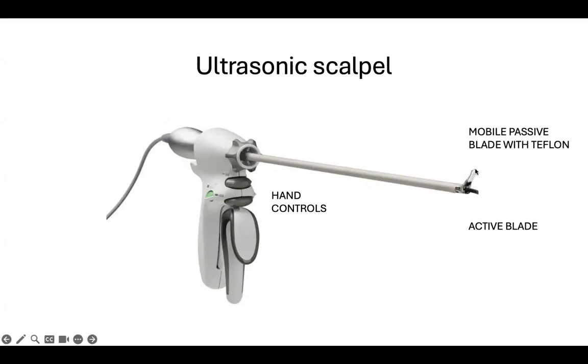this passive blade Teflon is going to get damaged slowly. It depends on how well you use the instrument, how capable you are, how much expertise you have. The more pressure, or if you start crushing the tissue or start activating this instrument even without any tissue in between, this blade is going to directly damage this Teflon, and there is going to be a groove formed. So the life of this instrument lasts as long as this Teflon coating is intact or at least semi intact. That is the entire key of this instrument.